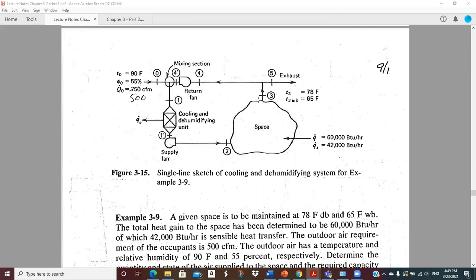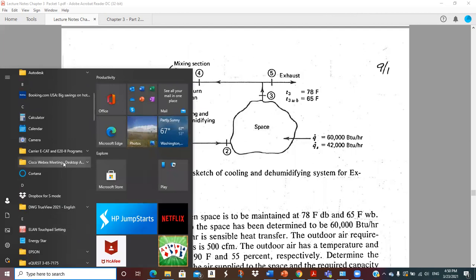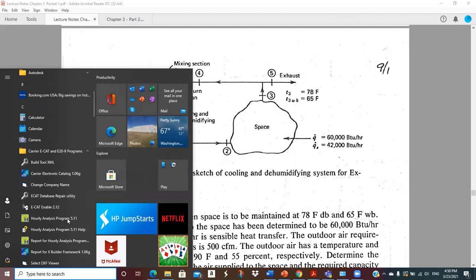We're going to run over this example problem again. This is one I think I had done previously, but it's pretty important stuff. This is where the rubber meets the road, so we want to go through this. What we see here is a space that someone has calculated loads on with a carrier program. The numbers they came up with were 60,000 BTUs per hour total and 42,000 BTUs per hour sensible. The difference — 18,000 BTUs per hour — would be latent load.